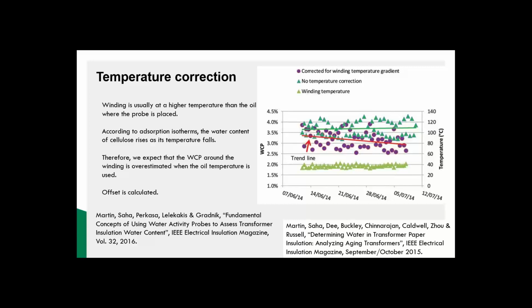Now, another thing which we get frequent comments about is to do with temperature correction. When we started trialing our algorithms on industry's transformers, we were also using dielectric response as a way of just verifying that what we're coming up with is right, it's working properly. One thing we very quickly noticed is that when we're using dielectric response, usually we are taking the temperature of the winding. In some cases, the transformer might be left to cool down because it has to be disconnected from the grid to actually do the measurement.